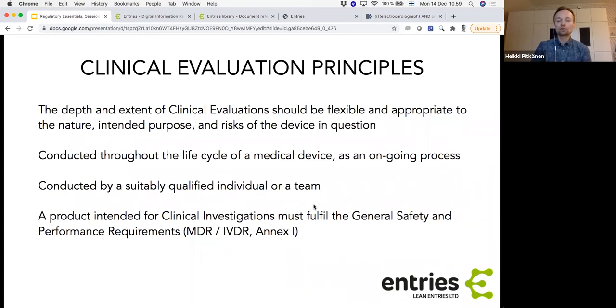So you need to make sure that if your device is an electromedical, it fulfills at least most parts of the 60601 standard. And for the ones that it does not, you will need to provide a rationale for the hospital you work with, for the authorities when you ask them for permission to run this investigation, for the ethics committee that takes their stance on whether it's okay to run the investigation. So maybe not all parts of the requirements are fulfilled, but you have enough understanding that it should be safe to investigate in the clinical setting.